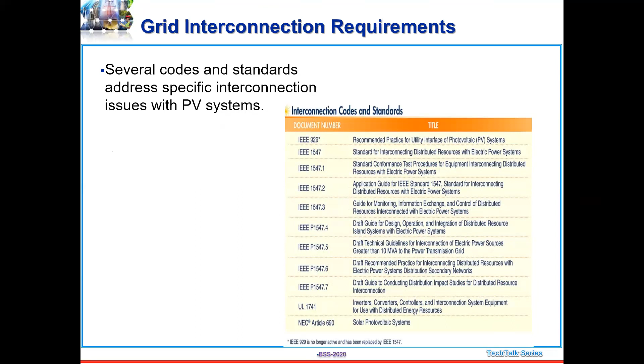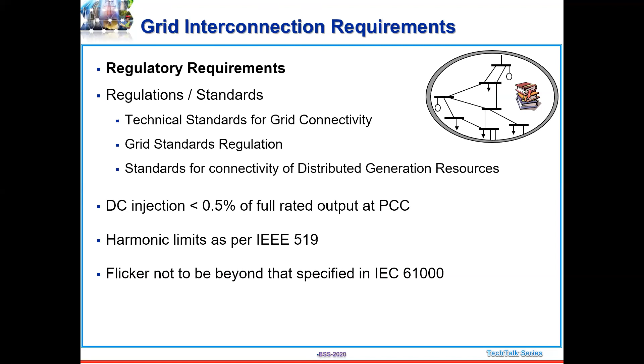DC injection should be less than 0.5% of full rated output at the point of common coupling. Harmonic limits should be as per IEEE 519. Flicker should not be beyond that specified in IEC 61000. So these are the regulatory requirements. Now, the system shall be capable of providing dynamic reactive power between 0.95 lag and 0.95 lead.